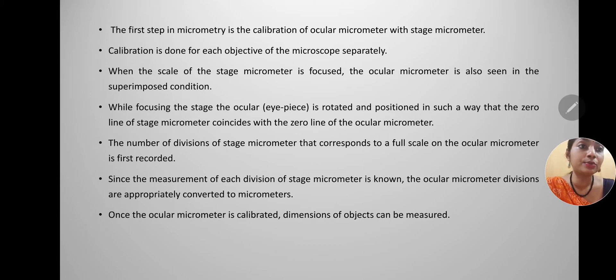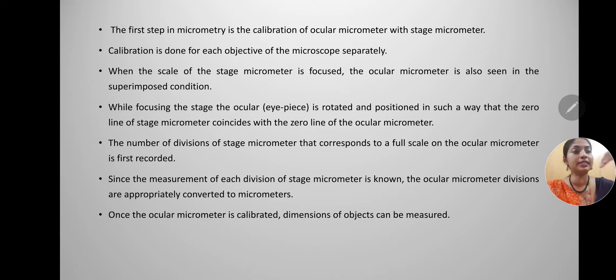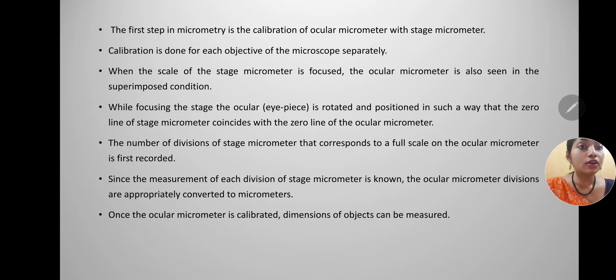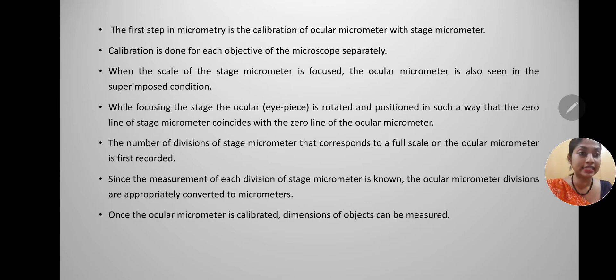When the scale of the stage micrometer is focused, the ocular micrometer is also seen in superimposed condition. We can see two different markings in the field of vision. These are superimposed so that the first line of the stage micrometer and the first etching on the ocular micrometer coincide. Once coinciding, the system is calibrated. The number of divisions of the stage micrometer that corresponds to a full scale on the ocular micrometer is recorded — that is, where the two next coincide exactly — and that gradation on both scales is recorded.